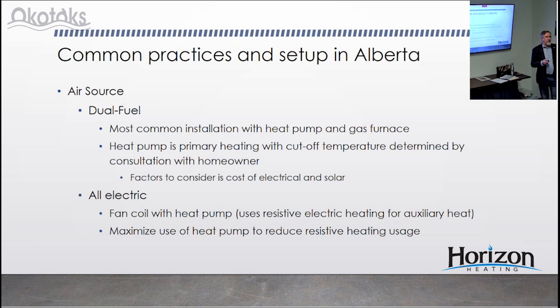Does anybody know why we don't run the gas furnace and heat pump at the same time? If we go back to that photo of the coil sitting above the furnace, the burner section of the furnace is below the heat pump coil. So if the furnace is on, it's boiling the refrigerant because it's firing at 200 degrees Fahrenheit or whatever coming out of there. That refrigerant's going to come back to the compressor and destroy the compressor because it's not in the right phase.